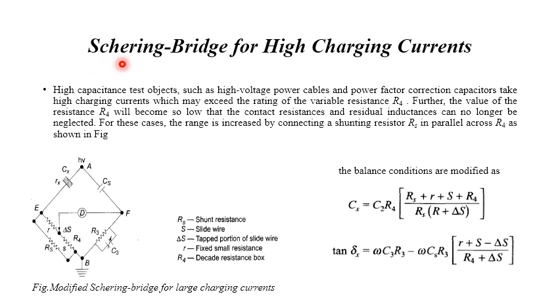The next one is the Schering Bridge in the case of high charging current. There are some test objects like high voltage power cables and power factor correction capacitors, which take a very high charging current which may exceed the range of the variable resistance R4, that is nothing but the standard value of the resistance, which you can see here, the R4, this is R3 and the C3, and this is the standard value capacitance, and we don't have the option to change this. However, these are kept as constants.